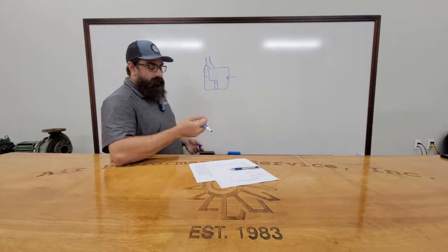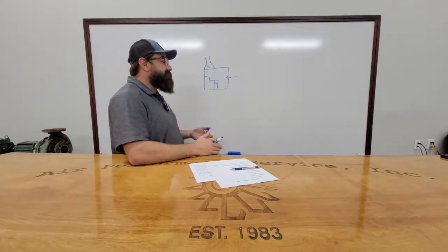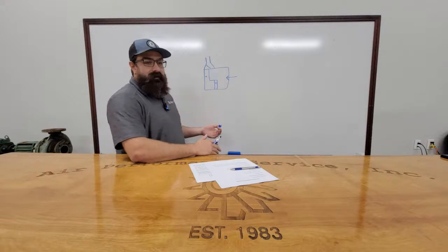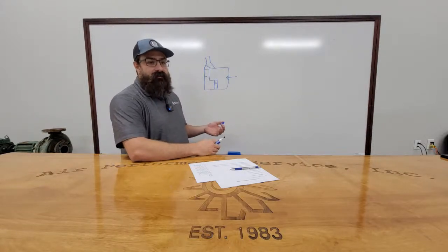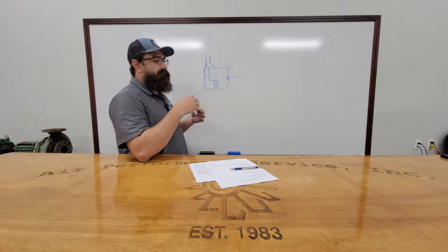Yep. So the reason when I said don't put a VFD on a multi-zone is they're designed to be constant volume. So all of your dampers are set up and all of your zone registers are set up to be constant flow.